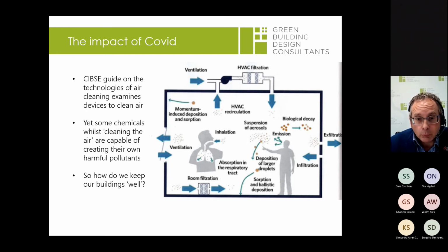CIBSE have been looking at options like displacement ventilation, bringing fresh air into buildings at low velocities, usually at ground floor level or through the raised floor. As hot air naturally rises, we extract at ceiling level, quickly getting any aerosol COVID or other diseases away from head height to the ceiling for extraction. It does seem fairly common thinking that fresh air systems should enter at low level and be extracted at high level, as quickly as possible.